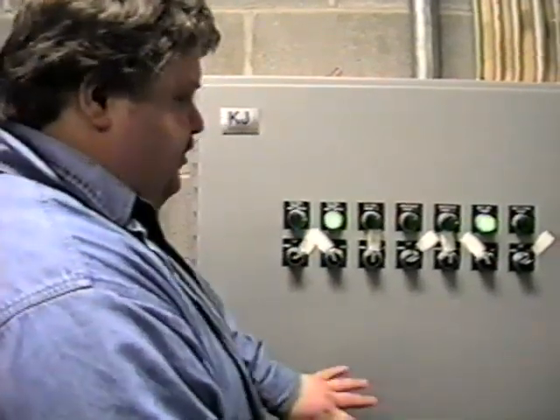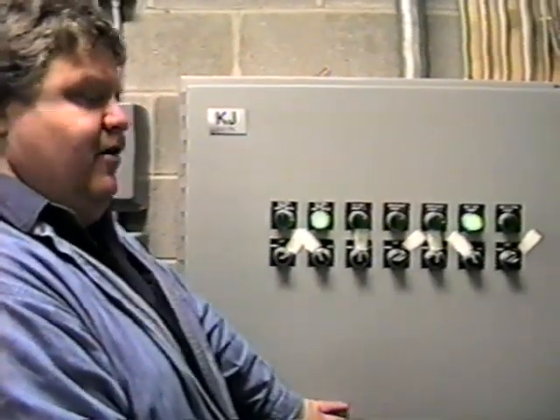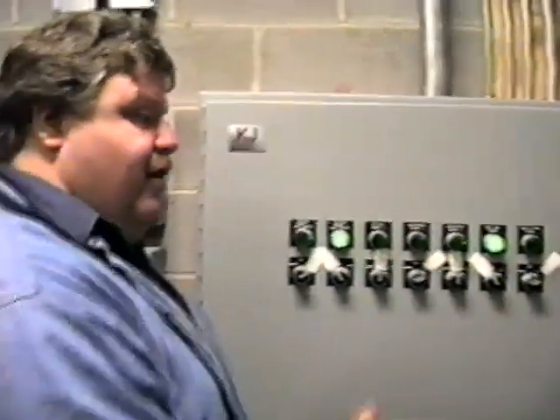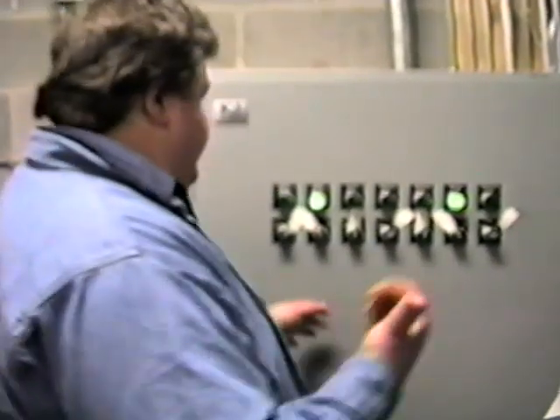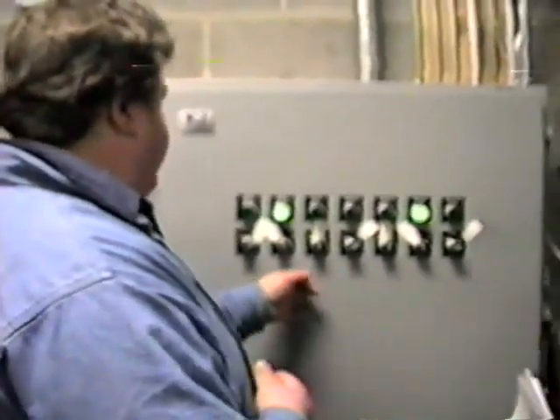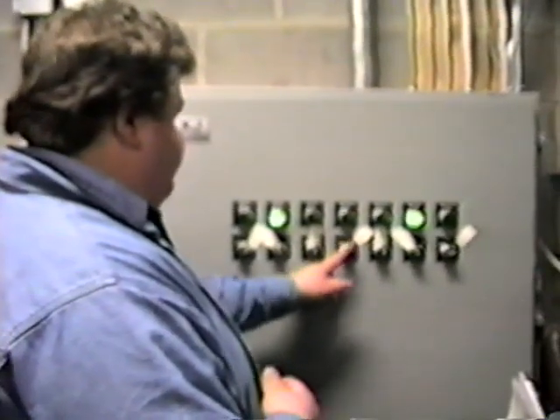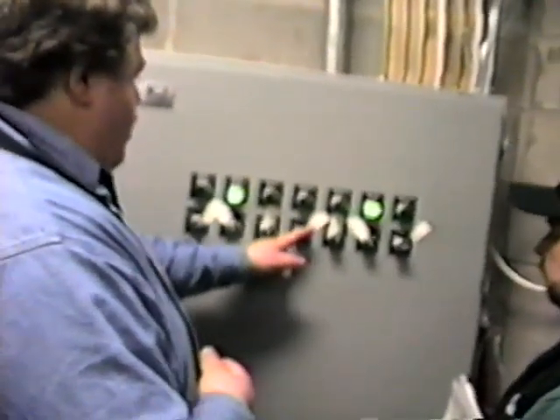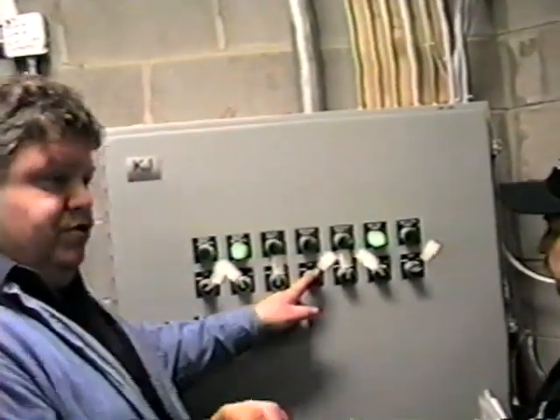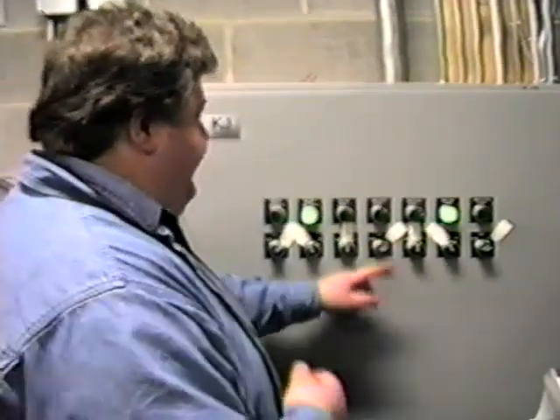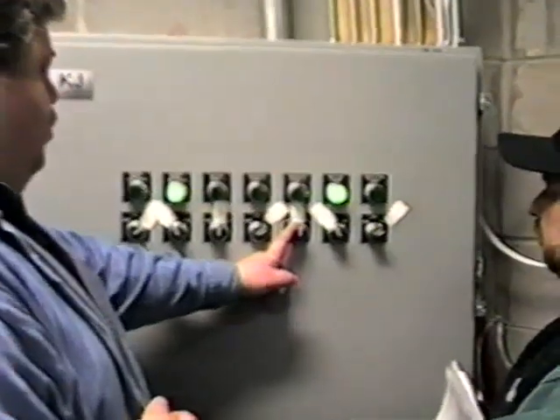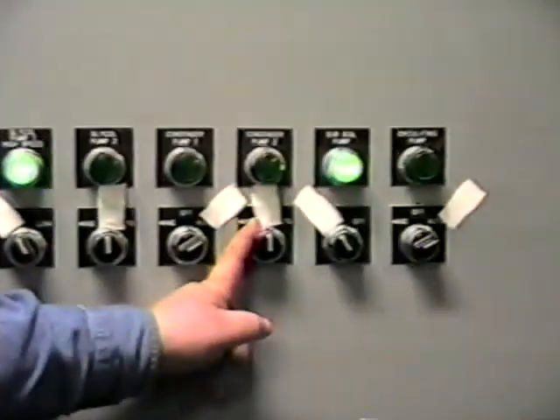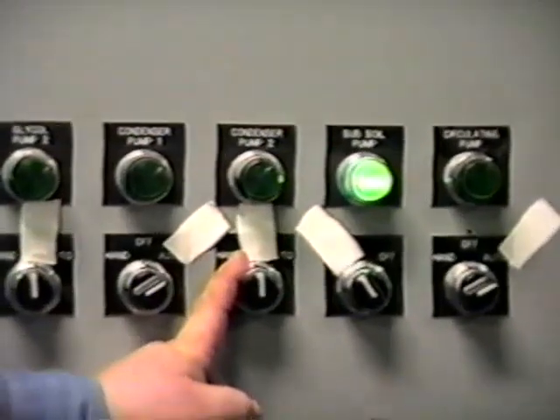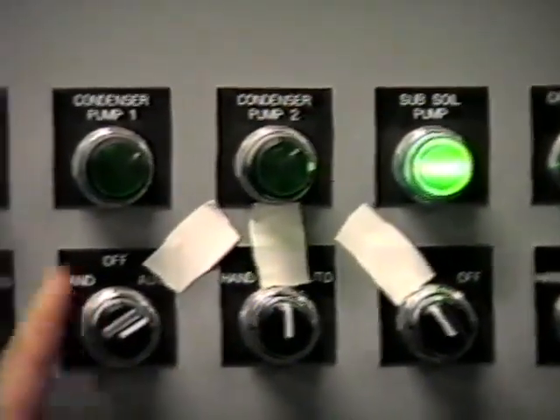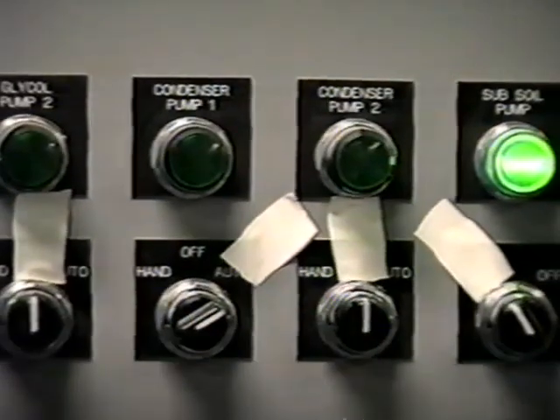There's a little readback switch in here on the starter that's sending a signal over there. Right now it's telling the chiller to turn on, but I've got to check to see if I still have temperature high enough to keep it off. Condenser pump should always be in automatic, and that's going to come on through your chiller. That's what's controlling that. This one is your backup pump, which I believe is hand position. I have to double check on that one. I think if this one were to fail, you put this one to hand position and let it run.